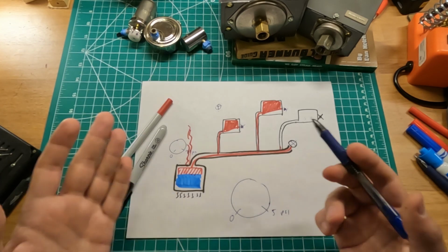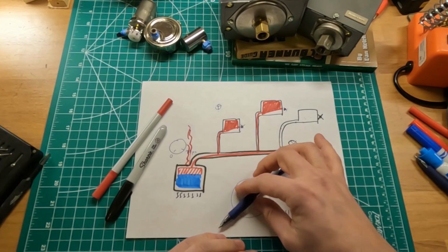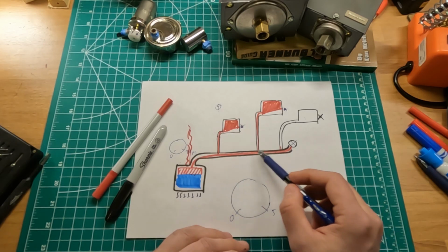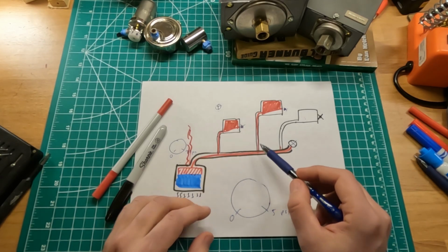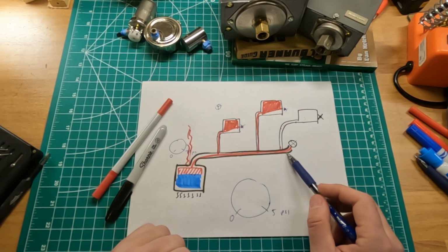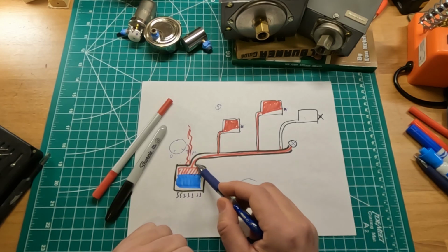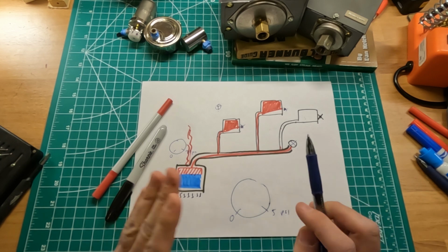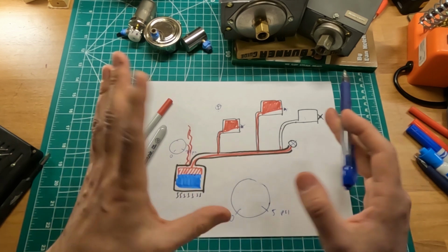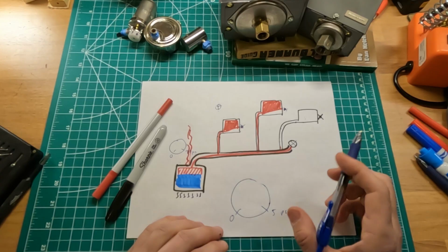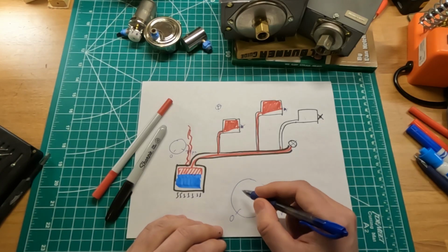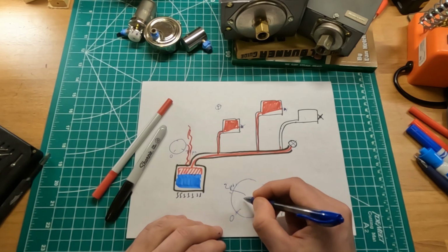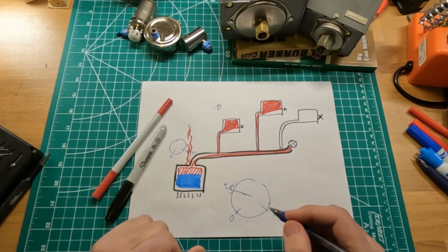But let's say one day you discover that at the beginning of the cycle, your pressure rises very rapidly. Why is it? It's probably because there's some kind of blockage in the system. The steam has nowhere to go. So because of that, the pressure stays inside the boiler, the steam stays inside the boiler, and you need to figure out what the problem is. But in essence, in a perfectly working system that's well balanced, there should be very little pressure.